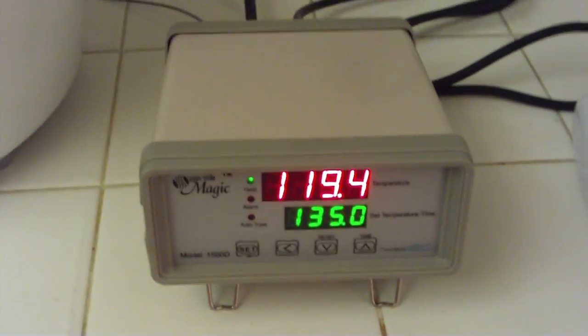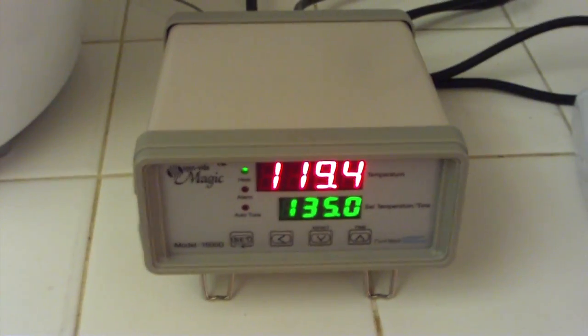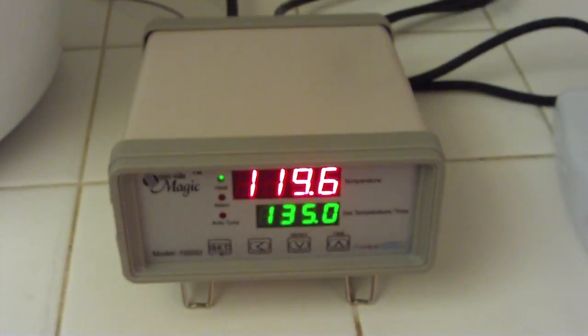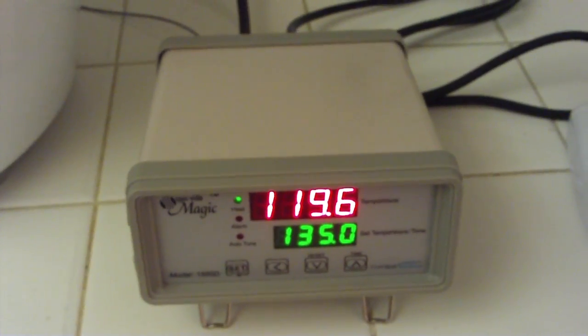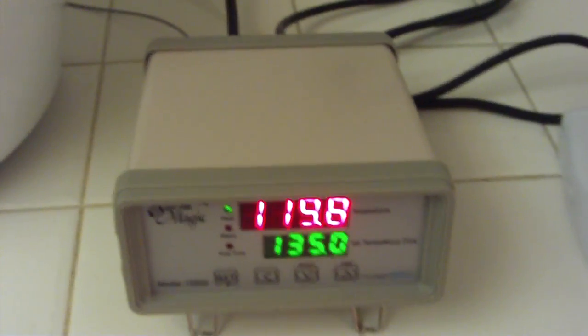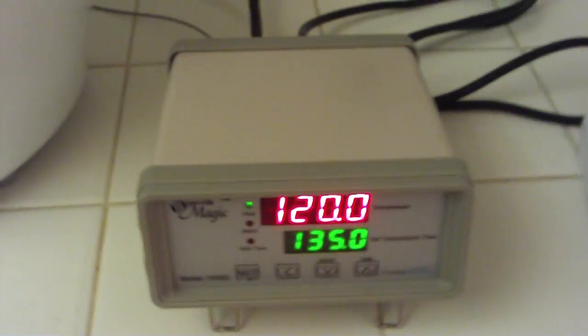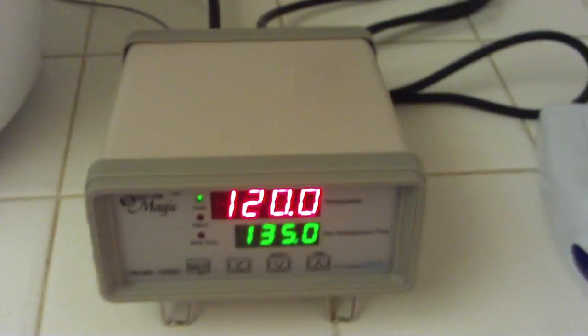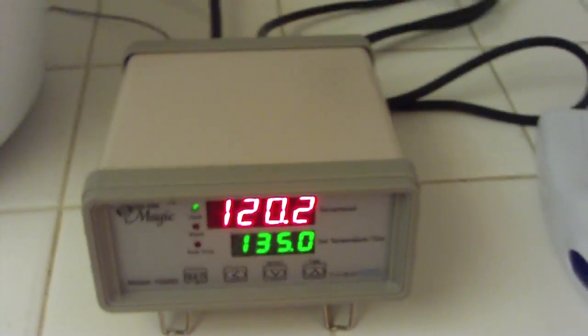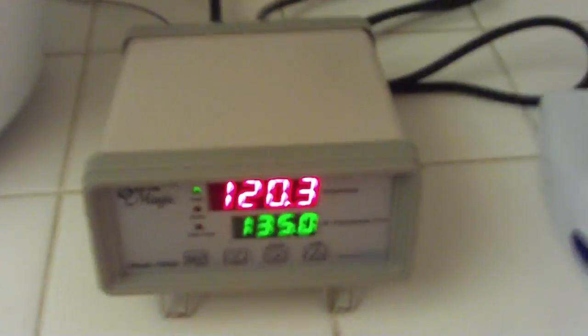The default temperature is 68 degrees. If it's below 68, it will not start. But you can actually adjust that. The idea is if the probe somehow falls out, the device would shut down, because it assumes that the ambient room temperature is around 68 degrees. But again, you can adjust that, your safety margins. I'll show you very quickly how to set this up.